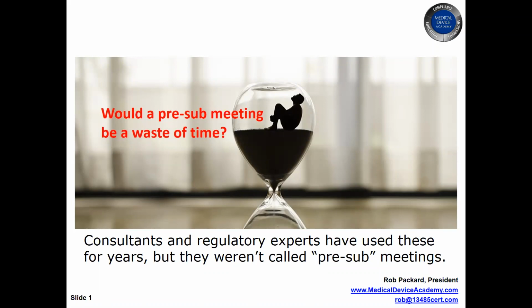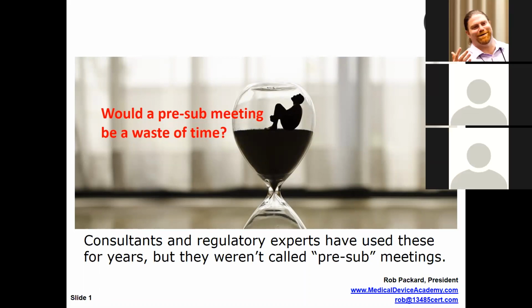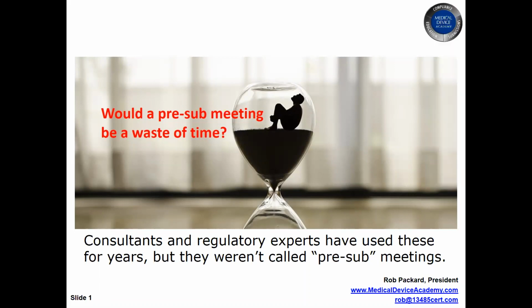And in the past, I actually made the statement, if you already have a special controls guidance document, or you have already done a submission of this device type and you're an experienced regulatory professional, you probably really don't need a pre-sub. And I regretted those words because the FDA made a couple of changes. One of them was to the biocompatibility guidance document that the FDA released in 2016. And then there was another one that they released around the same time on human factors.